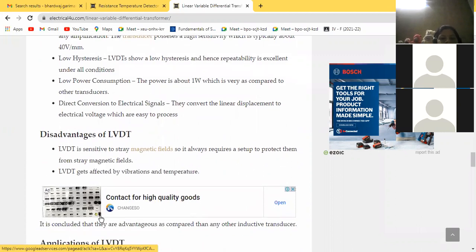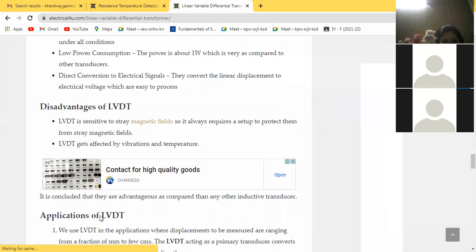Disadvantages of LVDT. LVDT is sensitive to stray magnetic fields, so it always requires a setup to protect it from stray magnetic fields. LVDT gets affected by vibrations and temperature. Next is application of LVDT. We use LVDT in applications where displacements to be measured range from a fraction of mm to a few centimeters. The LVDT, acting as a primary transducer, converts the displacement to electrical signal directly. The LVDT can also act as a secondary transducer. Example, the Bourdon tube acts as a primary transducer and converts pressure to linear displacement. And then LVDT converts this displacement into electrical signal, which after calibration gives the reading of the pressure of fluid.